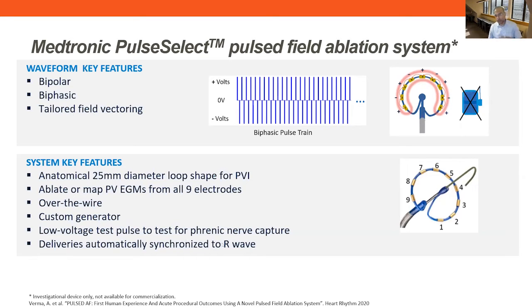There is a low voltage test pulse, which you deliver before you deliver therapy to make sure that you cannot capture the phrenic nerve, because in preclinical studies, we found that if you do not get any phrenic nerve capture with the test pulse, it is almost completely unlikely that you're going to cause any stunning of the phrenic nerve with PFA.